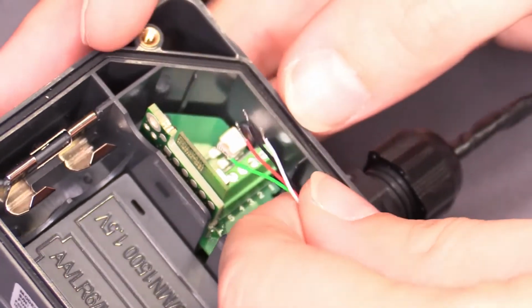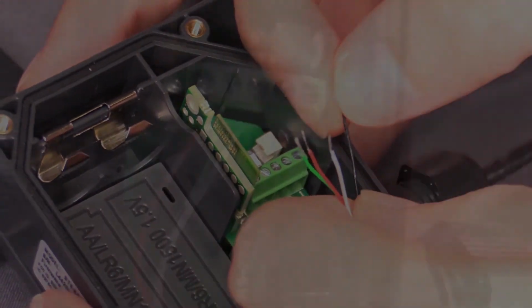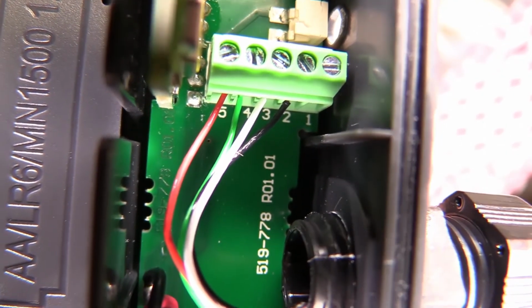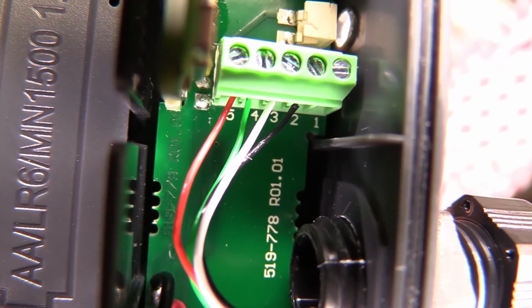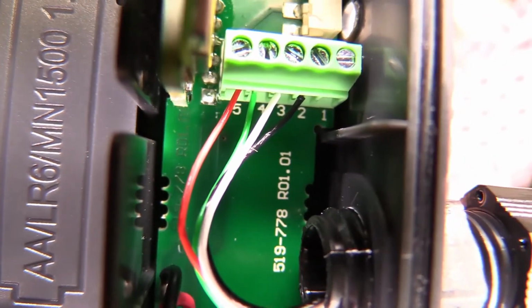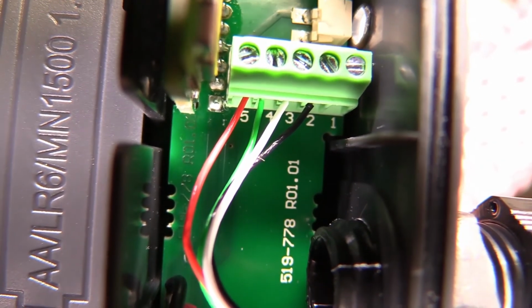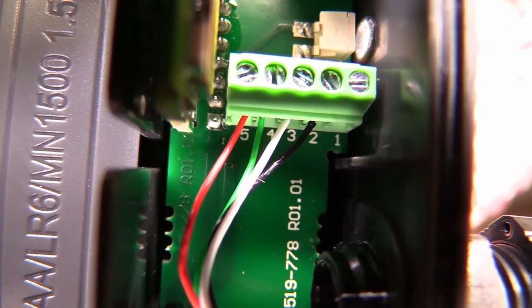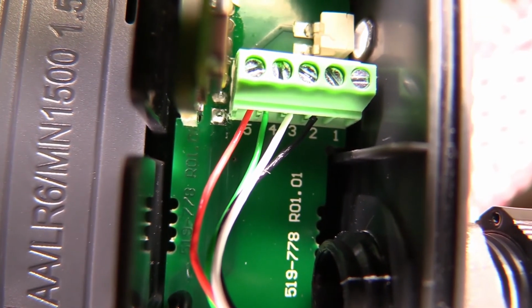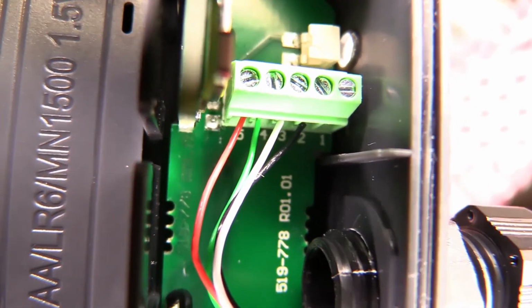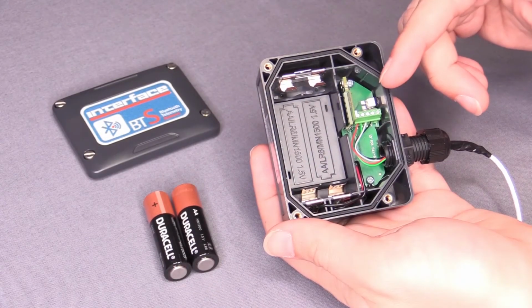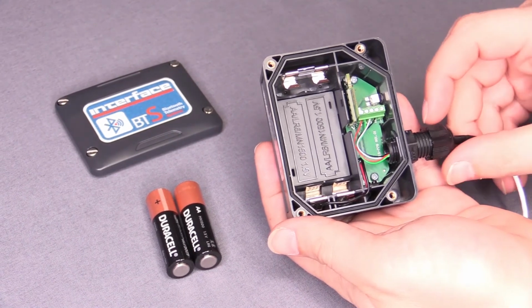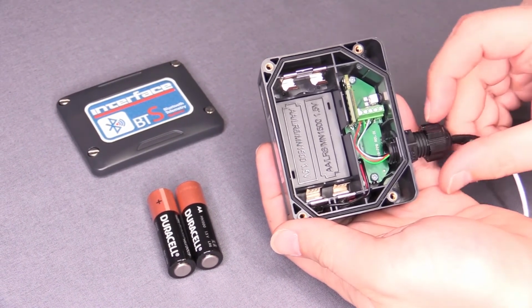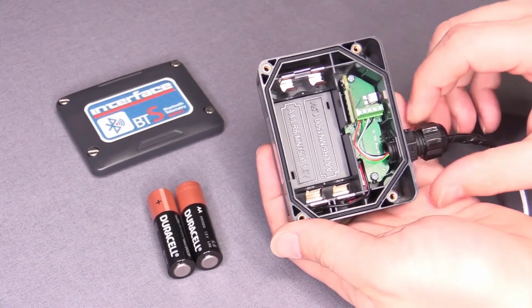Right. And the next thing we're going to do is put our four wires into the screw down terminal. Okay, so as you see here, we've put our black negative excitation wire into terminal 2. We have our white negative signal wire in terminal 3. We have our green positive signal wire in terminal 4, and we have our red positive excitation wire in terminal 5. Okay, once you've finished screwing down the terminals, you want to then tighten the gland nut to hold the load cell in place.